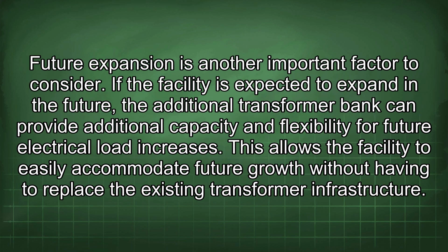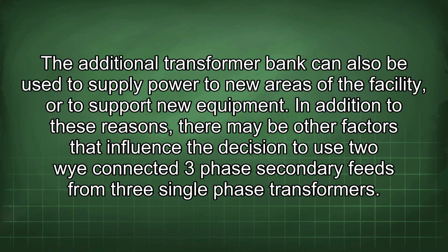Future expansion is another important factor to consider. If the facility is expected to expand in the future, the additional transformer bank can provide additional capacity and flexibility for future electrical load increases. This allows the facility to easily accommodate future growth without having to replace the existing transformer infrastructure.